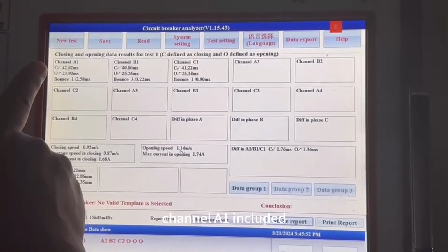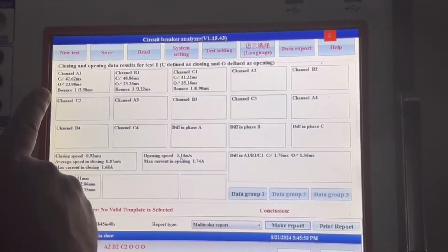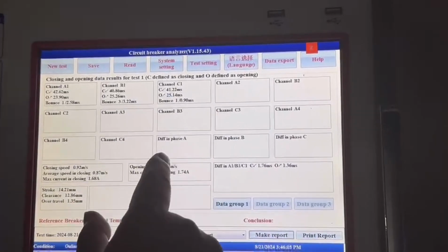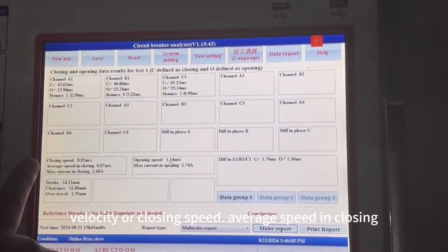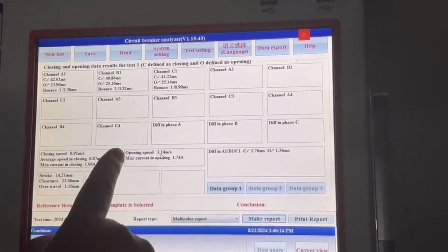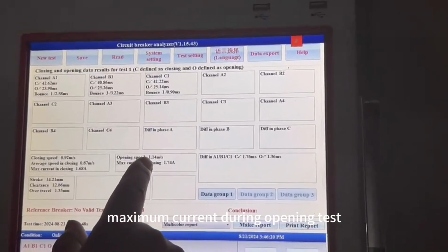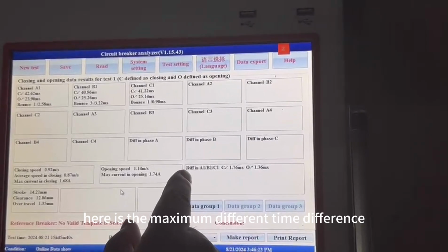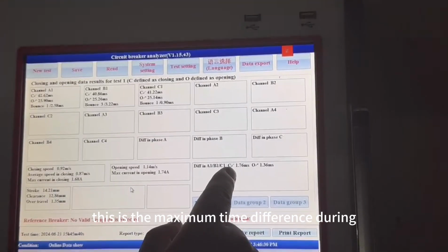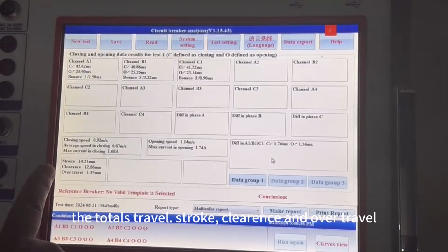Channel A1 includes closing time, opening time, bounce number, and bounce time during the closing test. B1 the same, C1 the same. And here is the closing velocity or closing speed, average speed in closing, maximum current during the closing test, and the opening velocity or opening speed, maximum current during the opening test. Here is the maximum time difference during opening. This is the maximum time difference during the closing test. And here the total travel or stroke, clearance, and over travel.